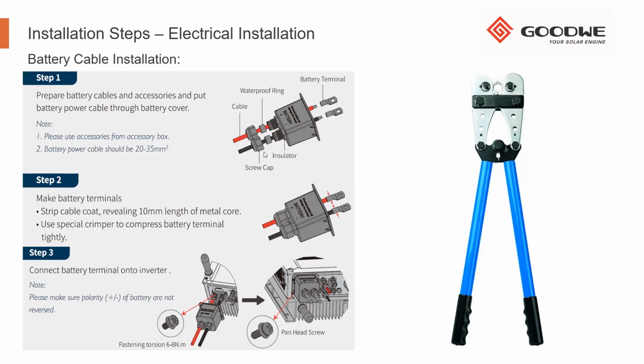Our glands below do allow for up to 35mm square cable. And always put your cable through the connector before you put your lugs on, because should you put lugs on first, you can sometimes battle to get it through the actual gland. And I stress, be very careful of the polarity. We don't want anything blowing up.